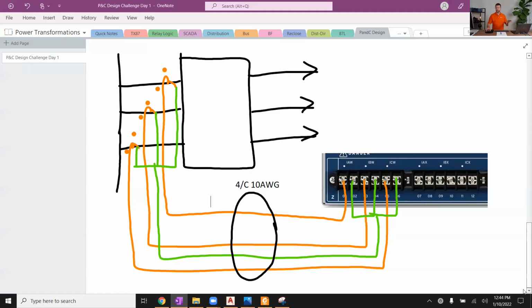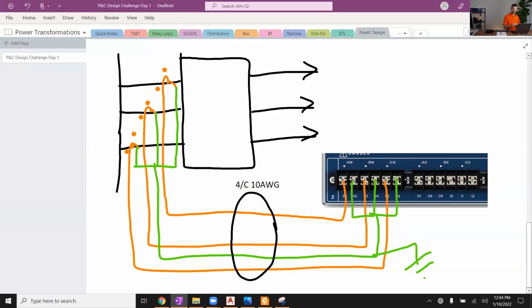We're going to ground it on the neutral part, but a critical part with CT wiring is that you ground it in one and only one spot. You don't want to have multiple grounds on your CT neutrals. So some companies' practice is to ground it in the back of the relay panel. Let's go ahead and draw that here. There's the ground in the back of the relay panel. Others may choose to ground it at the back of the circuit breaker cabinet where this common neutral is instead. Do not do it in both, do it in one or the other. But one and only one spot is an important concept for CT circuit grounds. Great point for bringing that up. Reading my mind of where I was heading down the road.